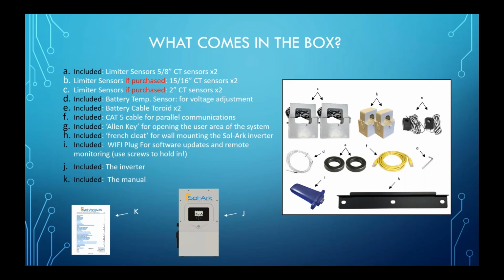D is the battery temperature sensor cable with the thermocouple at the end. E is a pair of the battery cable toroids. We'll see those in a couple slides on how to use them. F is the parallel cable. If you want to have the Sol-Arks talk to each other, if you want to stack them, that's the Cat5 cable. That's how they communicate. G is the little wrench in case you need to open the top. H is the French cleat. That metal bar right there is how you're going to mount the Sol-Ark onto the wall. Very, very easy. I is the dongle. The dongle is both Cat5 and Cat6 capable if you want to use a cabled solution with Ethernet cable. It's also Wi-Fi capable. And then, of course, the inverter and the manual come in the box as well.